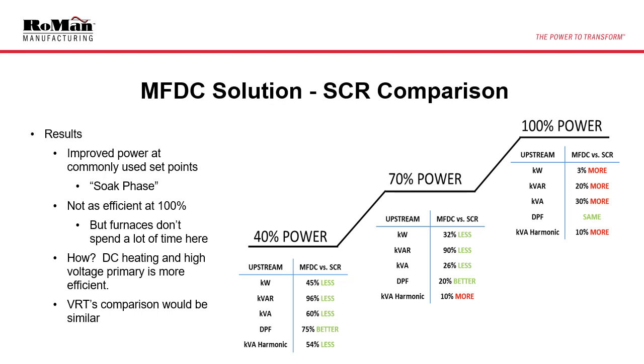Here are the results. You can see that we have lower power consumption across the board at commonly used set points. This means that if your furnace is in a soak phase at a set point of 40%, you have 45% less kilowatt consumption, 75% better displacement power factor, and 60% less kVA. We may not be as efficient at 100%, but furnaces don't spend a lot of time here. How is this possible? DC heating with high voltage, high efficiency power delivery is inherently better. VRTs were not included in this comparison, but are estimated to behave similarly to SCR controls.